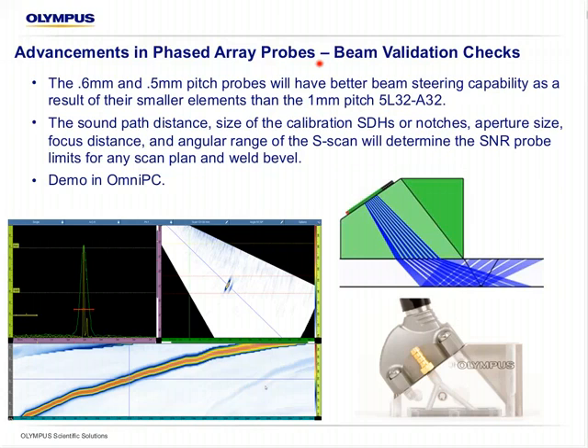The 0.6 millimeter pitch of the A31 or 0.5 millimeter pitch of the 5L64A32 will have a little better beam steering as a result of their smaller elements than that of any 1 millimeter pitch probe like the 5L32A32 or Pipe Wizard or A14 probes. The sound path distance, size of the calibration target, or side drilled holes or notches, the size of the aperture, the total number of elements, the focus, and the angular range will all determine the SNR probe limits for any scan plan or weld bevel.